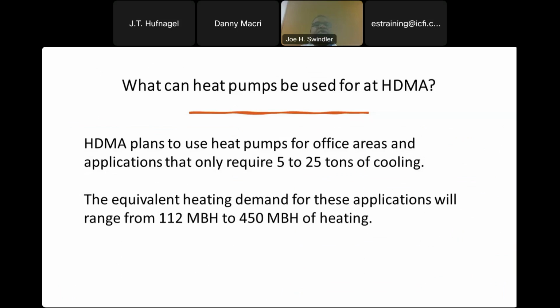So in summary, the plan at Honda: we plan to use heat pumps for office areas and applications that require 5 to 25 tons of cooling. Just to give you a general idea, the equivalent heating demand for these applications would be 112 MBH up to 450 MBH. So the lower range is for the South and the higher range is for Canada. And our southernmost plant in the US is Lincoln, Alabama. Next slide.